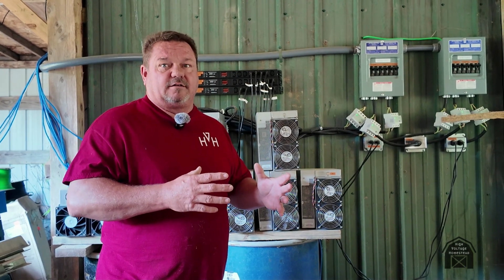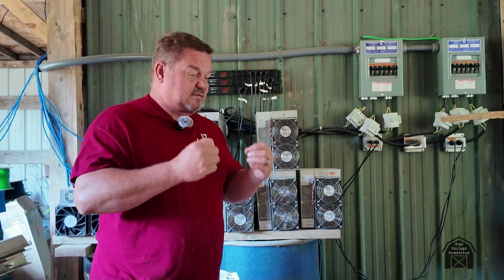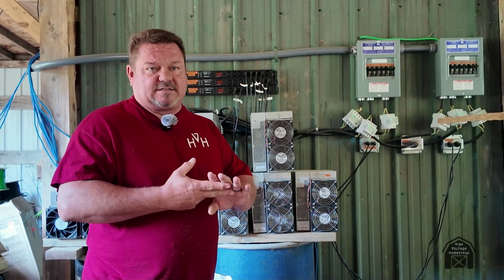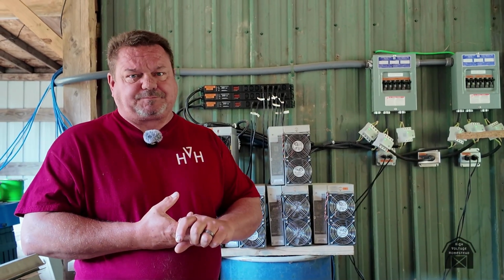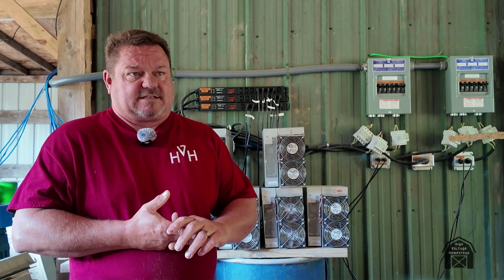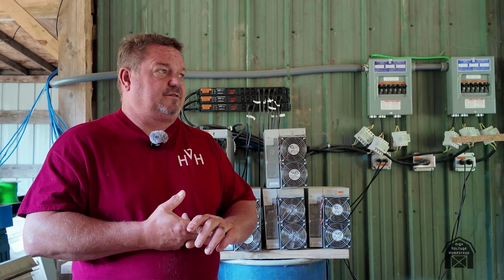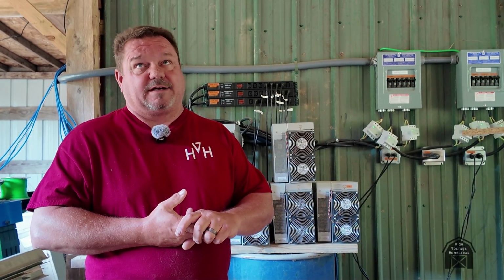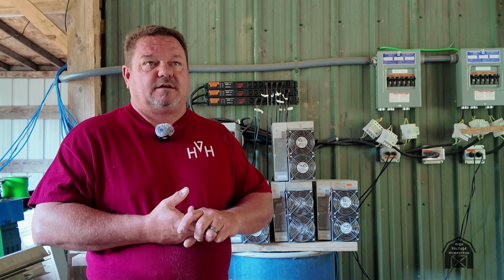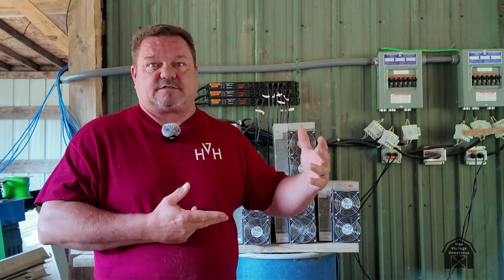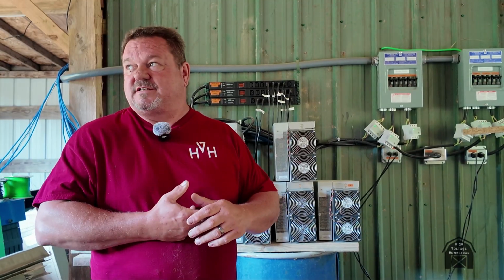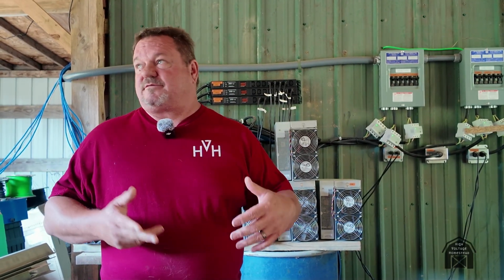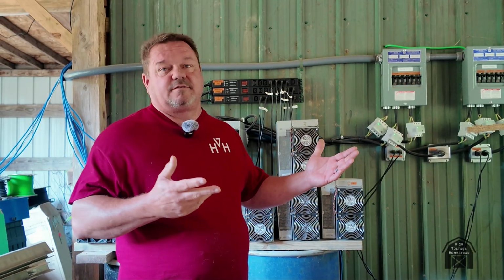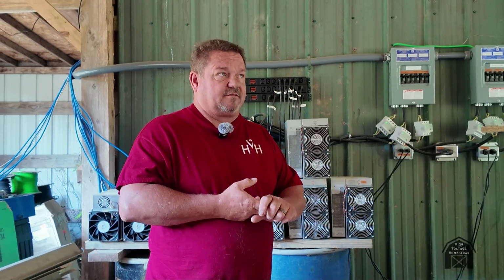But I do want to move them inside and get them out of the open area here, and I don't want fans running in there. I want it as quiet as I can get it. And the other reason that I wanted the water cooling is, I have a basically unlimited supply of water that's at 65 degrees, so I can use that to cool them at no additional expense. And water cooling tends to work better than air cooling, especially over the duration of the year. It's consistent. The water temperature fluctuates maybe 3 to 4 degrees, whereas air temperature fluctuates 40, 50 degrees or worse.